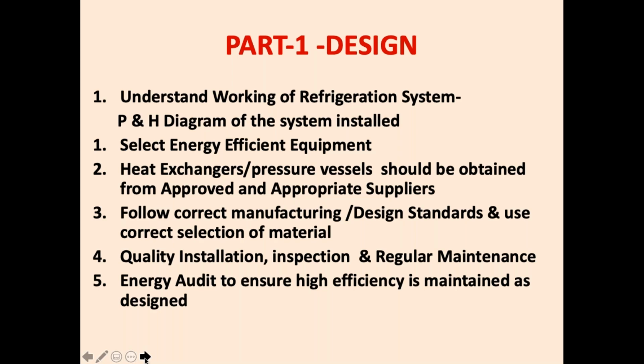Follow correct manufacturing design standards and correct selection of material. As I already told you, don't use non-standard material for pipes, for pressure vessels, for everything. Then quality installation, inspection, and regular routine maintenance. Very, very important to see whether our parameters are as per the design or they are deviating from the design. Energy audit to ensure high efficiency is maintained throughout is very, very essential.